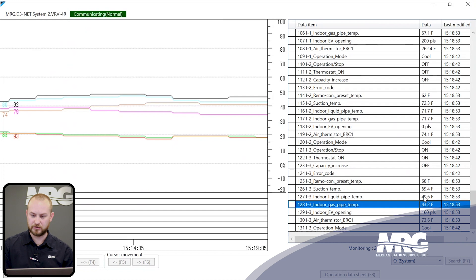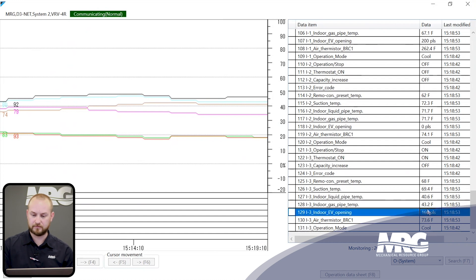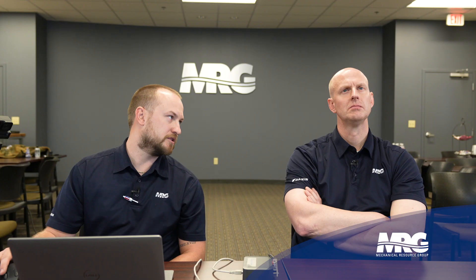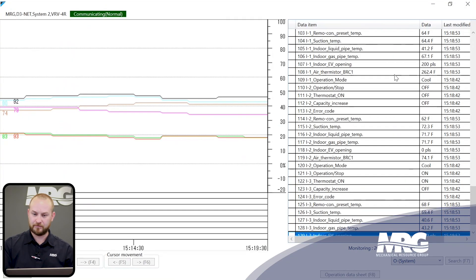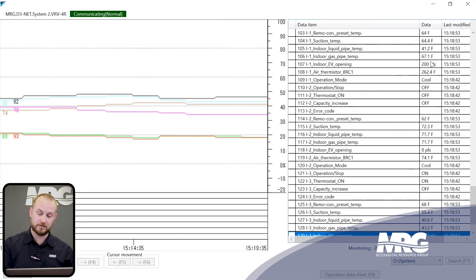We do have one unit down here with some really low temperatures — 43 and 40.6 degrees — and it's at the minimum position of 160 pulses. To clarify: on VRV3 the minimum is 200 pulses; on VRV4 it's 160. So this unit is at absolute minimum, and look how low those temperatures are compared to the first unit that's at a more open position.